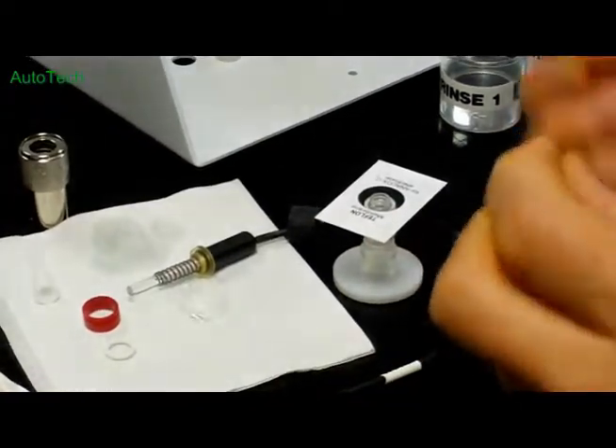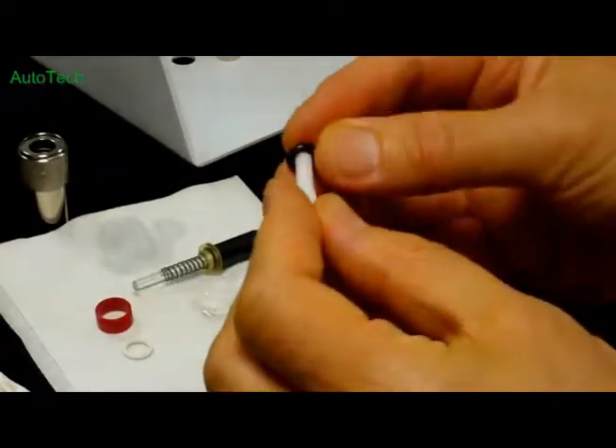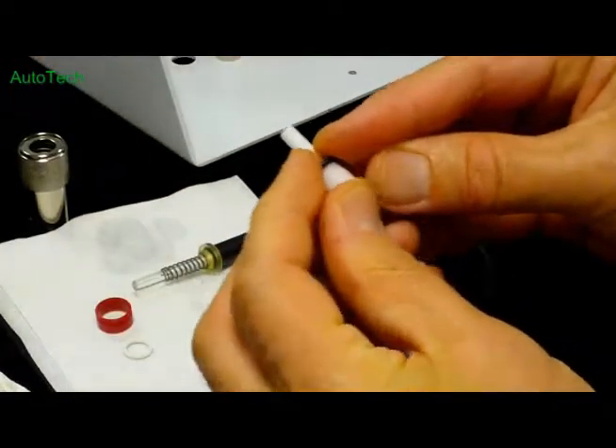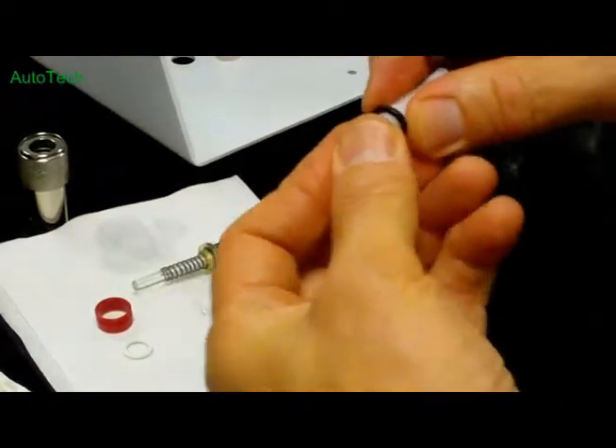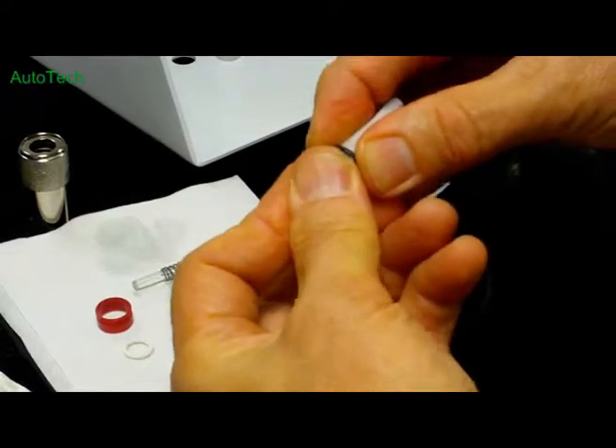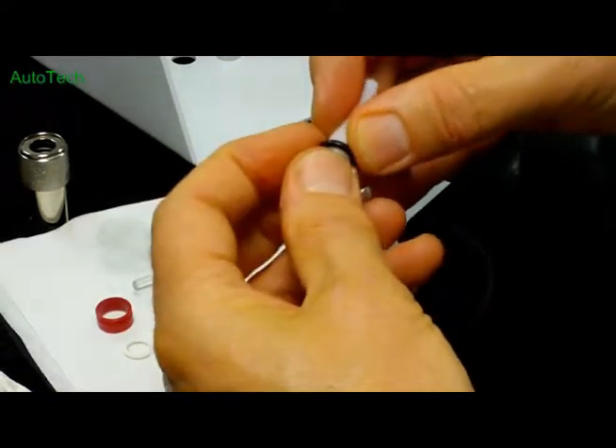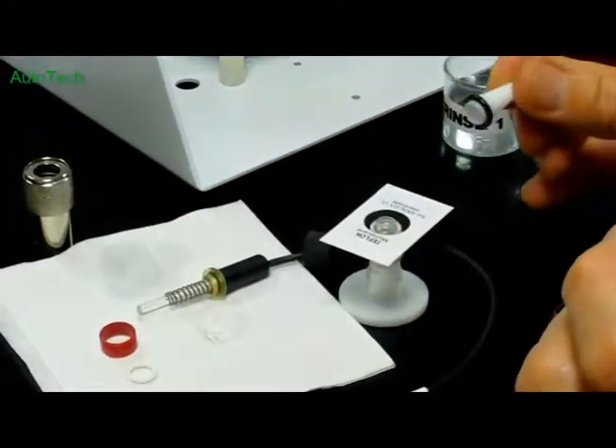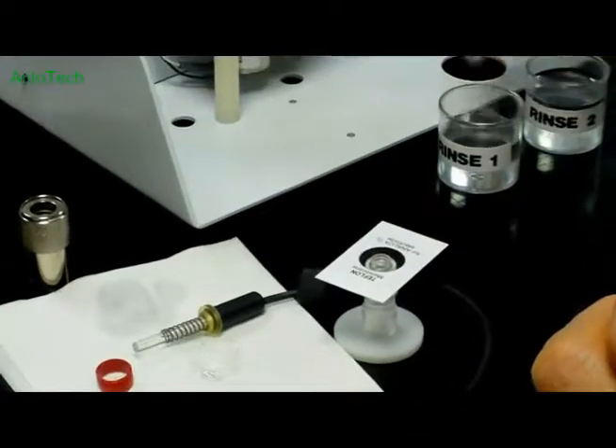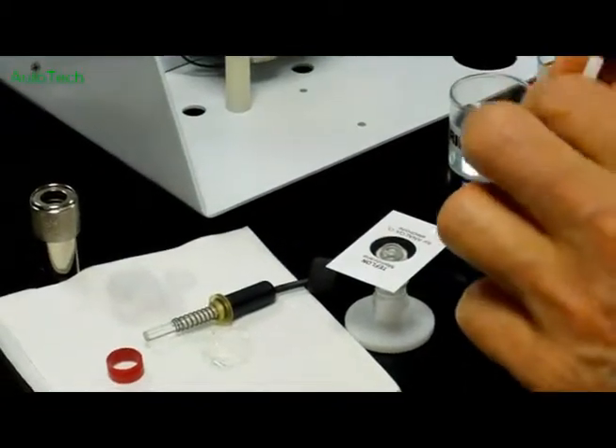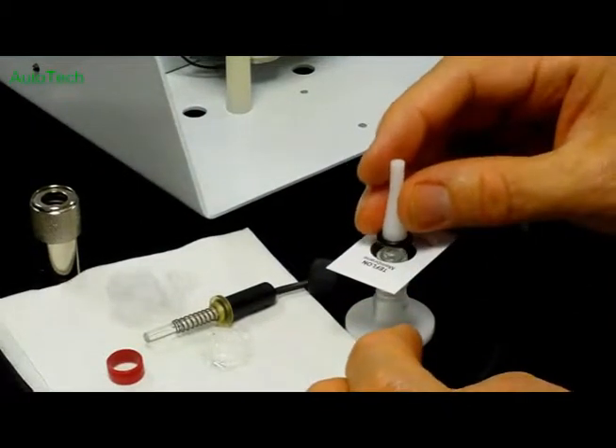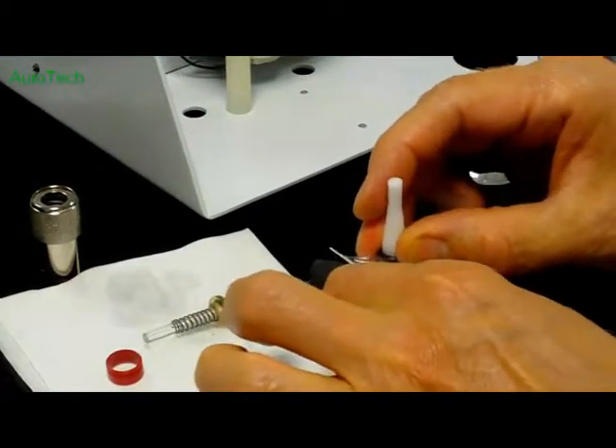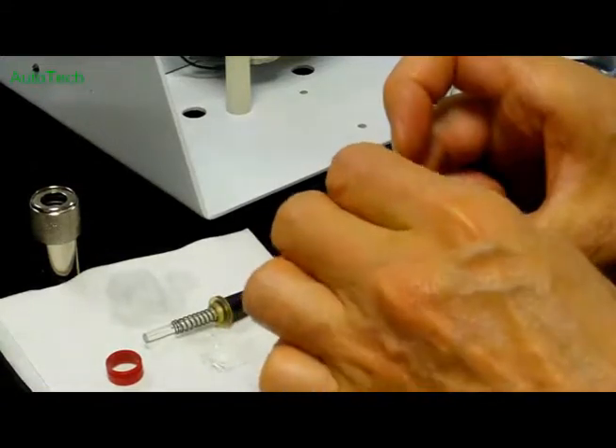Now it's okay to reuse the O-ring mounting membrane two or three times. So position that on the O-ring mounting tool as close to the end as you can. And then to make it easier to slide this onto the membrane, just dip that in some water. And then slide it down over the jacket like so.